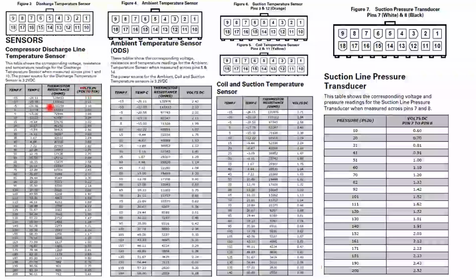Here's our chart. This is in your service facts in the outdoor unit. If you don't have the service facts on site and you need it, please call tech services so we can email it to you, or send you the snippets from this. But this is pretty important. Here's our discharge temperature sensor. That one has the color codes. I'm missing some parts in this, but it'll tell us exactly where the discharge temperature lands on this pin right here. It's usually mounted on the right-hand side.